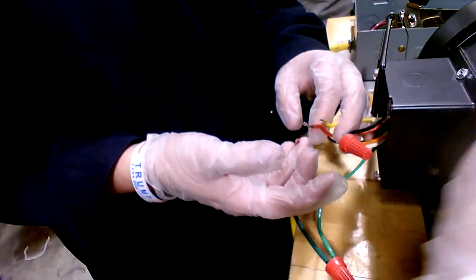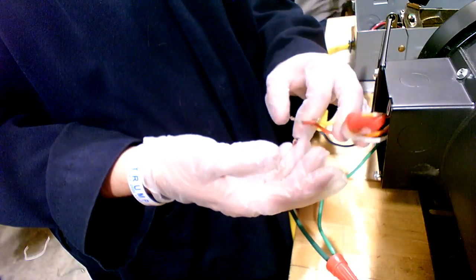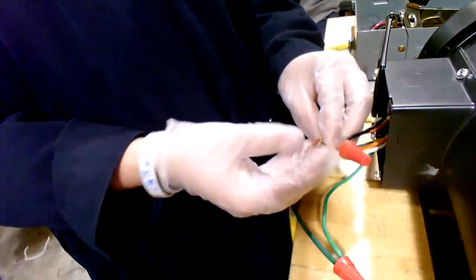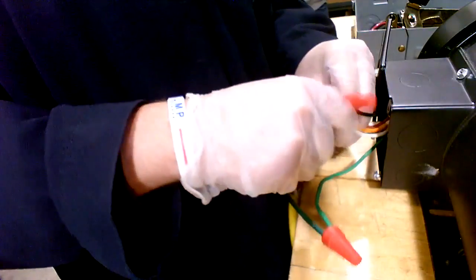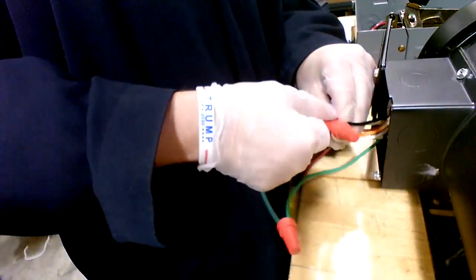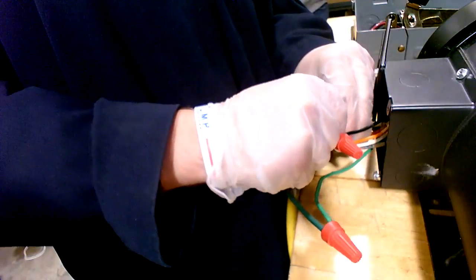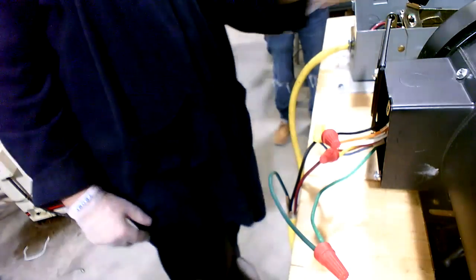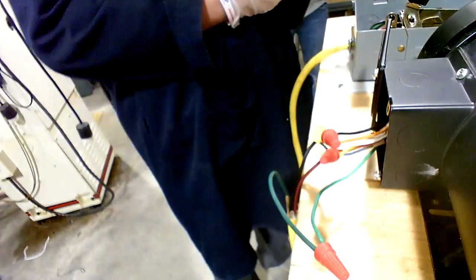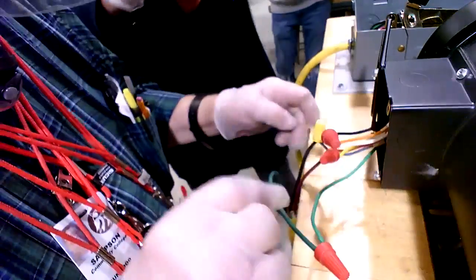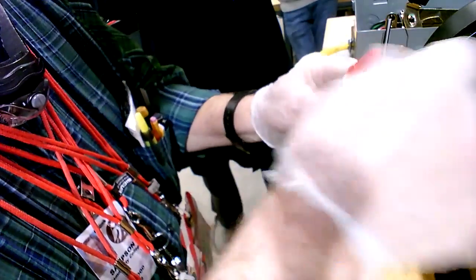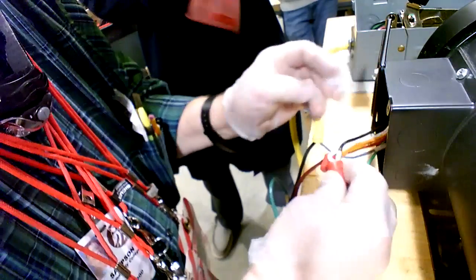So in the middle of it, that red's coming out, it'll be orange, black, and white in the middle. And then on the bottom, it'll be yellow and red, exactly. And what you're doing is you're flipping the start winding that contains that capacitor. You're changing the entire start circuit that includes a winding and a capacitor, without changing the polarity of the main windings, making it opposite from the main windings on the inside. So you've got yellow and red this time for one line. That's correct. And then your orange, black, white. That's correct. Now the motor's going to go counterclockwise.